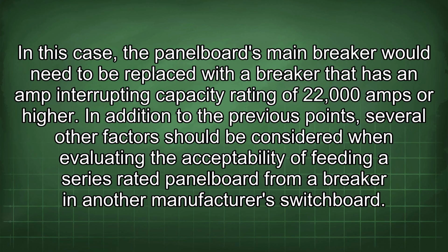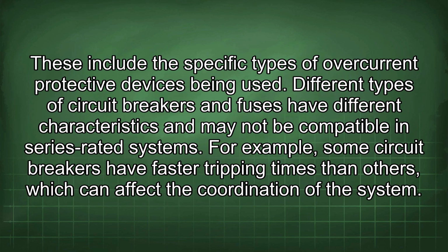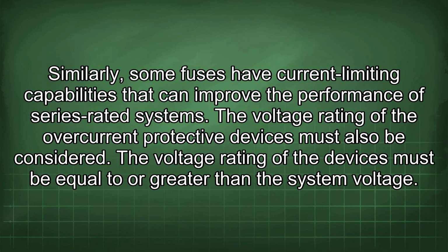In addition to the previous points, several other factors should be considered when evaluating the acceptability of feeding a series-rated panelboard from a breaker in another manufacturer's switchboard. These include the specific types of overcurrent protective devices being used. Different types of circuit breakers and fuses have different characteristics and may not be compatible in series-rated systems. For example, some circuit breakers have faster tripping times than others, which can affect the coordination of the system. Similarly, some fuses have current limiting capabilities that can improve the performance of series-rated systems.